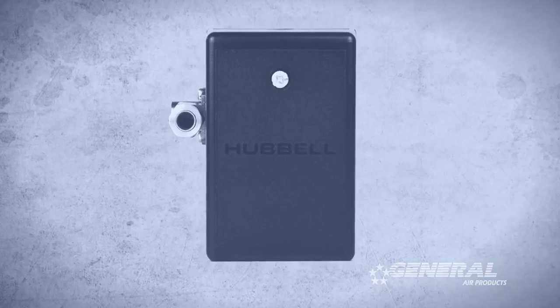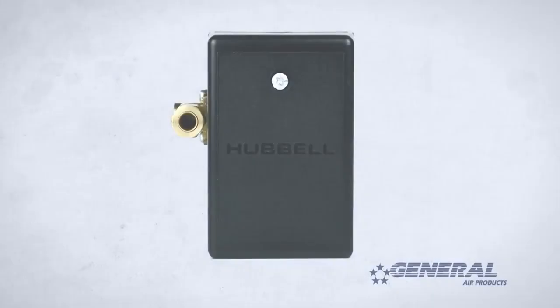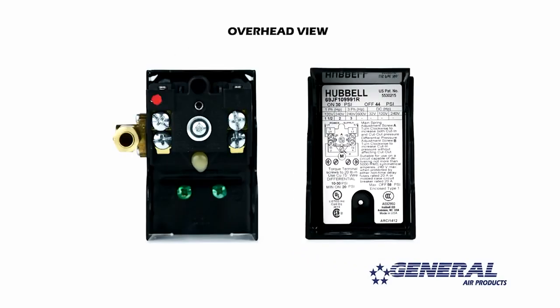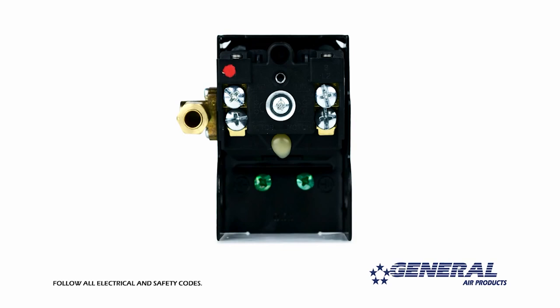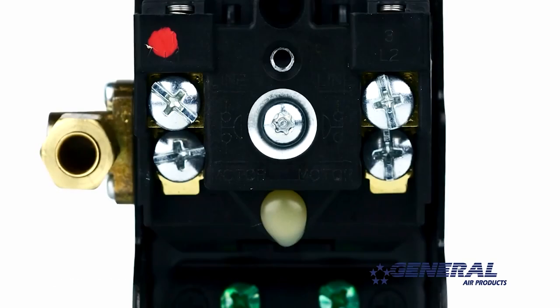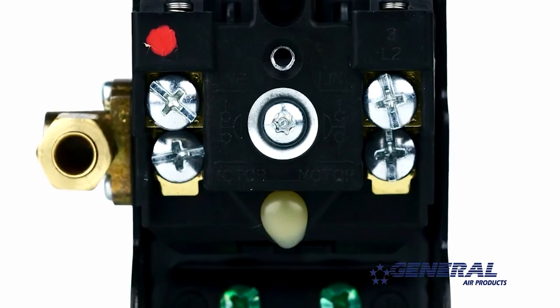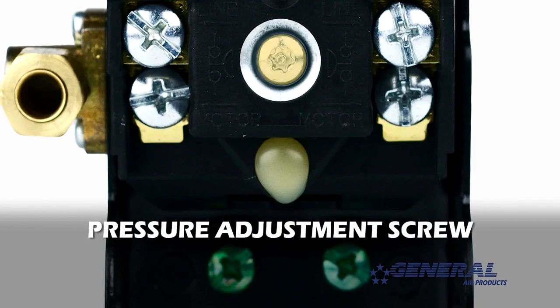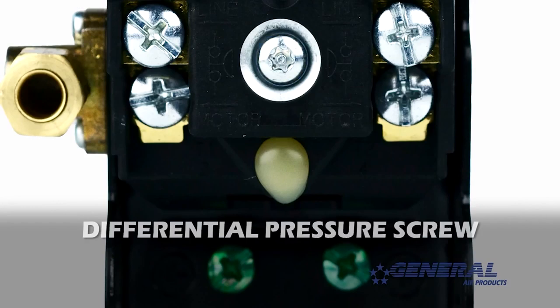The key to adjusting the pressure switch correctly is knowing which parts you'll be working with. Begin by removing the cover. Note that there are pressure switch adjustment procedures inside the cover of every one of our pressure switches. The first part of the pressure switch I want you to take note of is the electrical connection terminals for incoming power and power to the motor. This is the pressure adjustment screw, which we'll be turning to adjust the pressure range as we move forward. And this is the differential pressure screw. Do not touch the differential pressure screw.